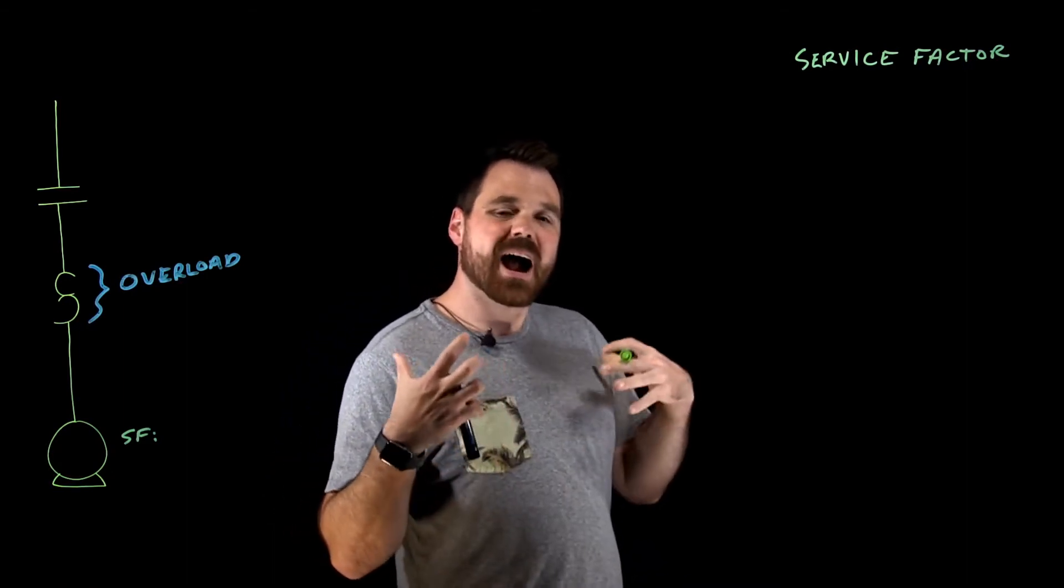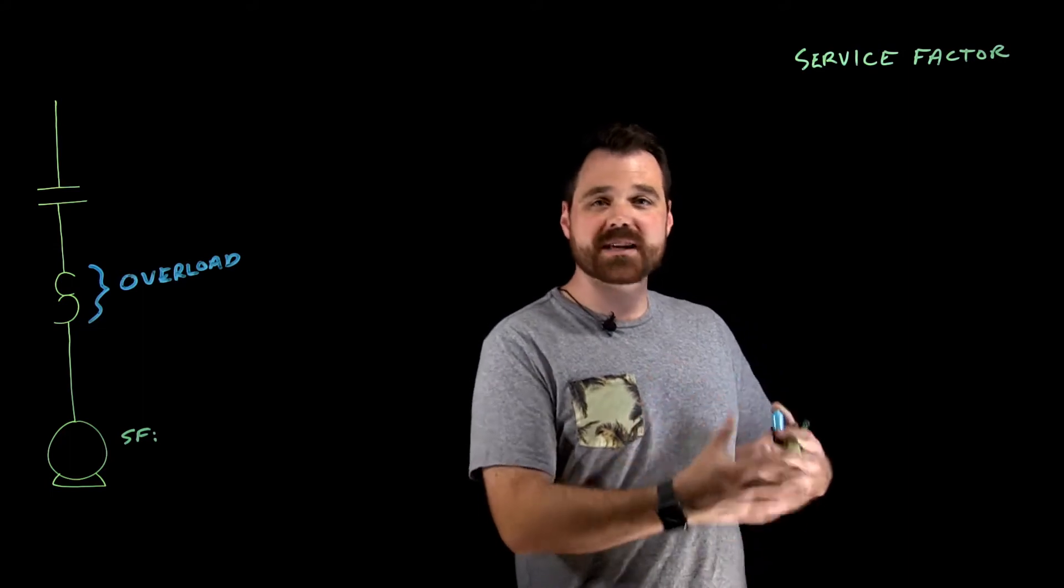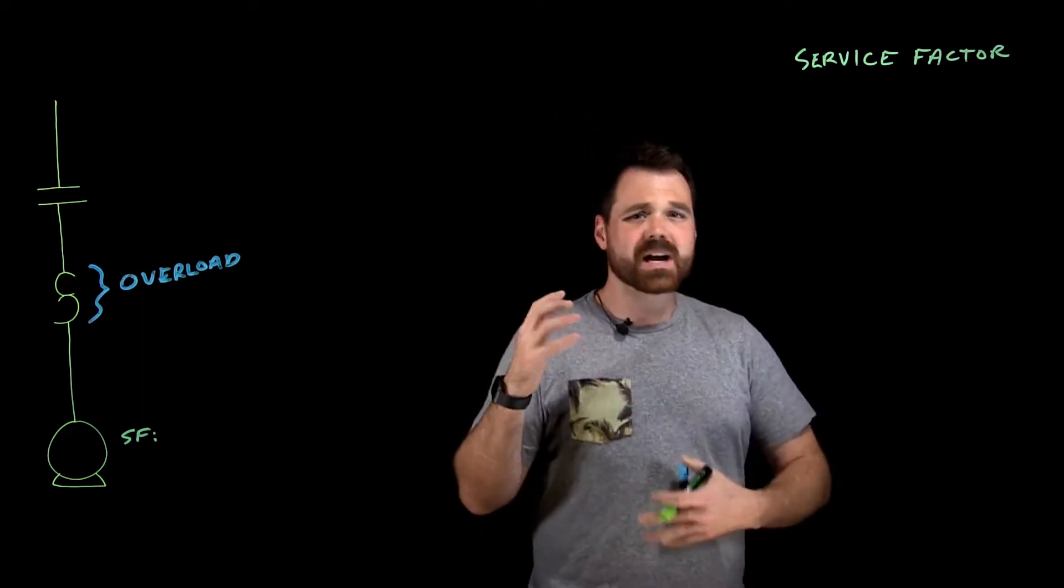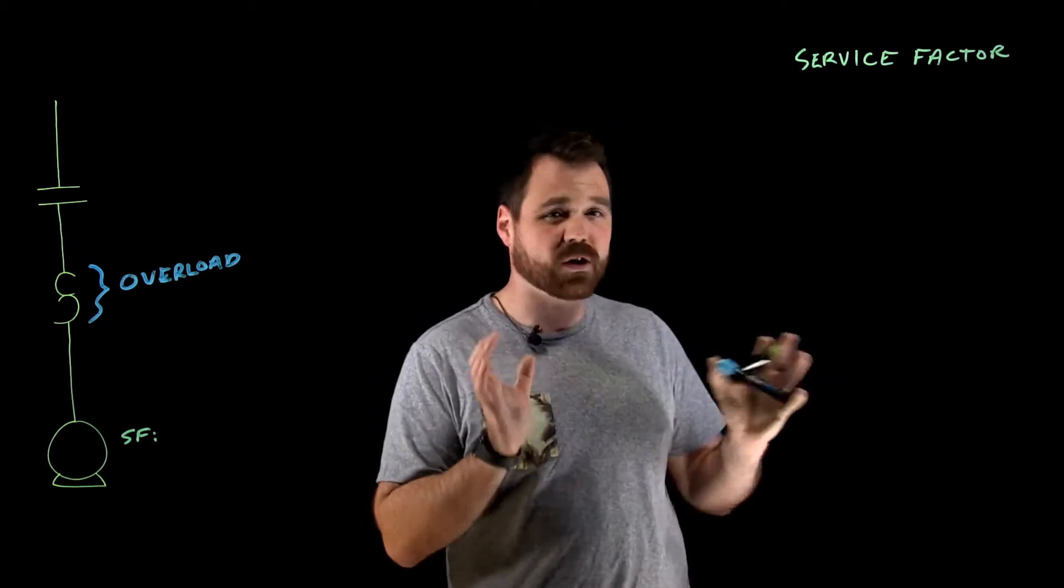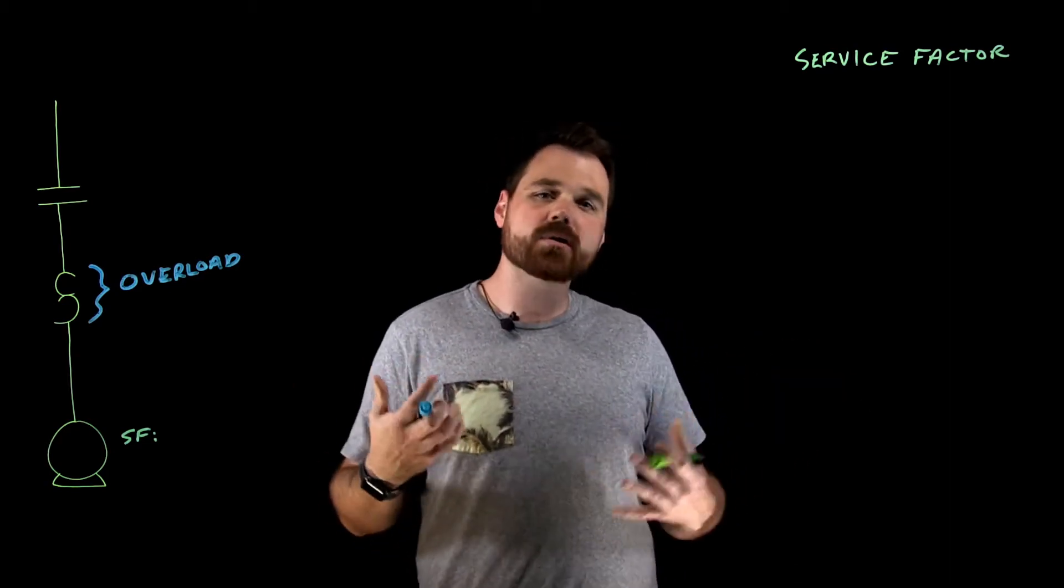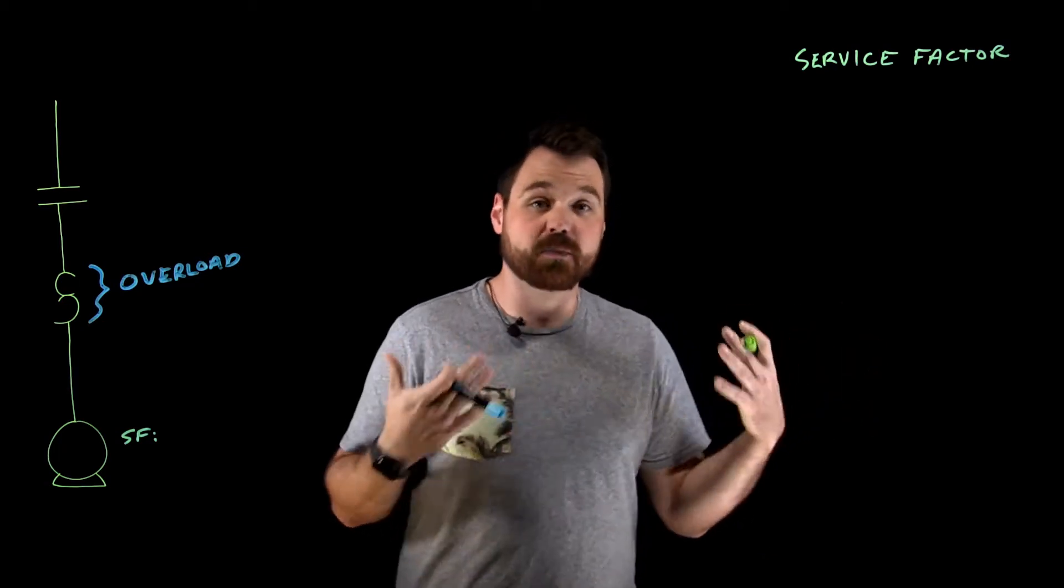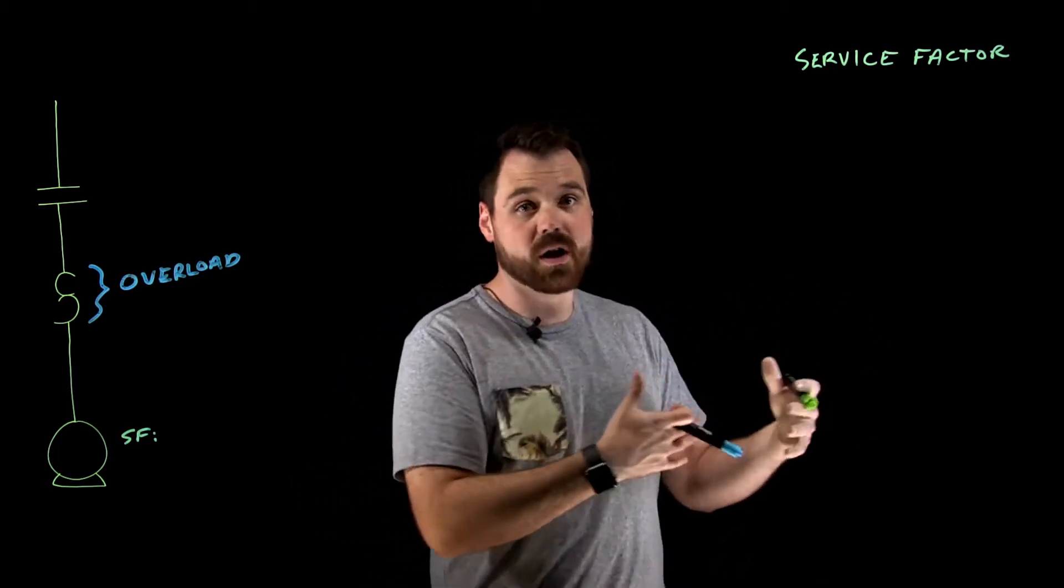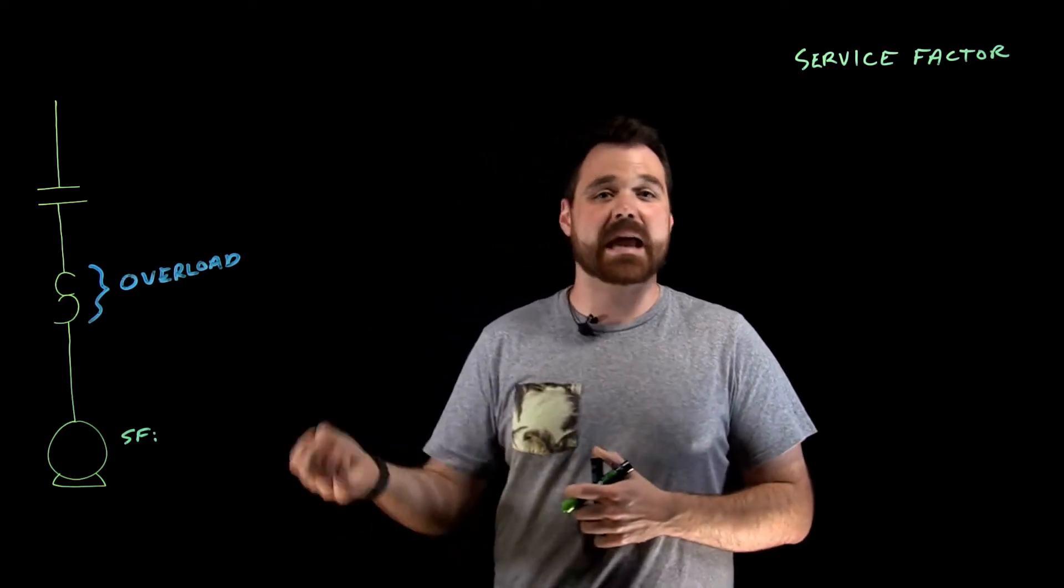That number tells us how much load I can put onto that motor before I start to do damage to the motor. So a typical service factor is going to be between one and 1.4. So if a motor is stamped with a service factor of 1.2, I can put 1.2 the load on it or 120% of the load on it before I start to damage the motor.